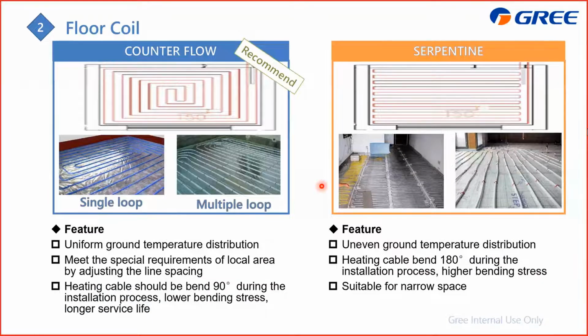And this is the requirement for the floor coil. When you install the floor coil, there are two patterns, which are the counter flow or the serpentine. And we recommend this one. This can ensure the temperature is even. And you can also see that for the pipe inside, it's only 90 degree bending. For this one, you need to bend 180 degrees, which is not that good for the water pipe.